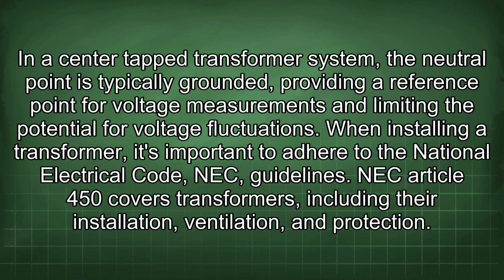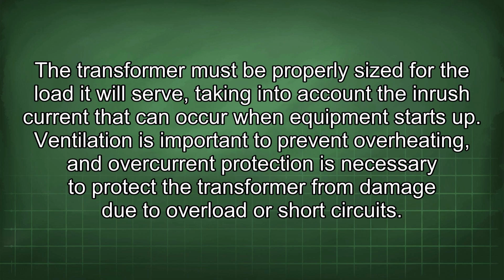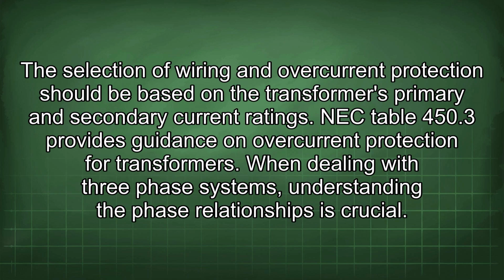When installing a transformer, it's important to adhere to the National Electrical Code (NEC) guidelines. NEC Article 450 covers transformers, including their installation, ventilation, and protection. The transformer must be properly sized for the load it will serve, taking into account the inrush current that can occur when equipment starts up. Ventilation is important to prevent overheating, and overcurrent protection is necessary to protect the transformer from damage due to overload or short circuits. The selection of wiring and overcurrent protection should be based on the transformer's primary and secondary current ratings. NEC Table 450.3 provides guidance on overcurrent protection for transformers.